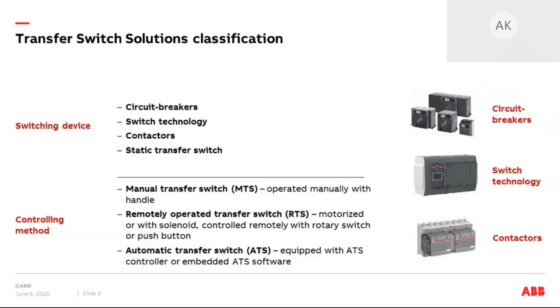Various transfer switch solutions exist on the market and all these solutions can be differentiated by two distinctive features. First, by switching device type — they can be based on electromechanical devices such as circuit breakers, switches (also known as changeover switches), or contactors. Transfer switches can also be static, based on solid-state power electronics.